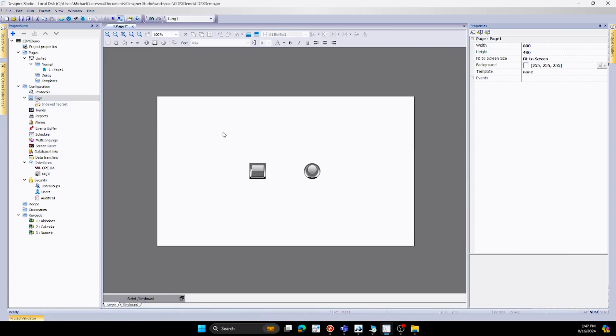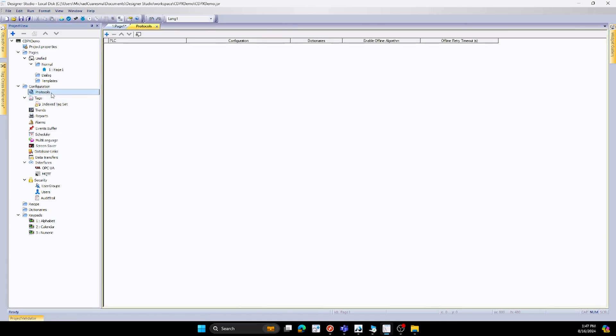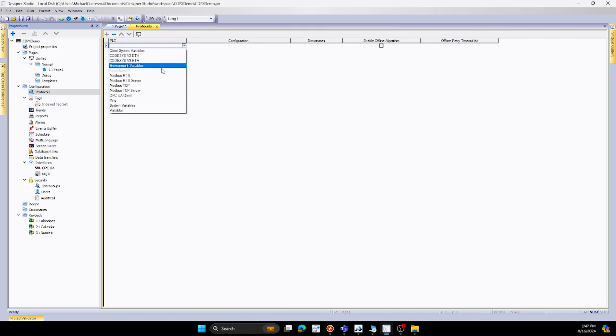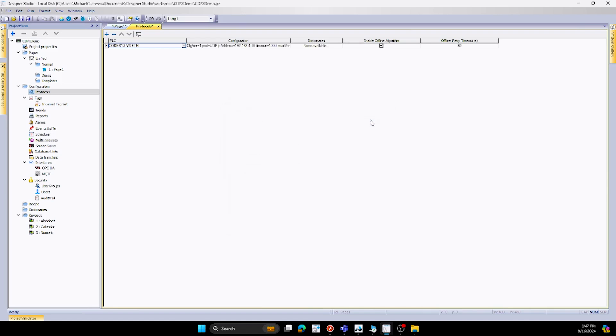The next thing that we need to do inside our HMI project is to set up the protocol. So we'll go to protocol here, we'll hit the plus button, and you'll notice that we have different options right here. For us, we'll be using CODESYS V3, and once we hit that, we'll see this window pop up, and what we want to do is type in the address of the PLC. So mine is 192.168.4.10. So once that is done, we have set that up.